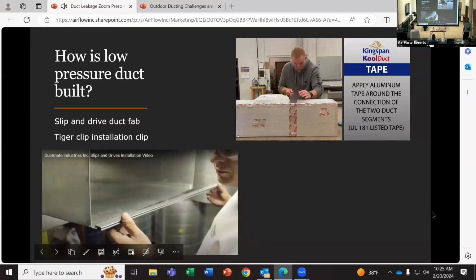You guys get the gist of it, right? So that's low pressure duct. On the left, what he's building right now without any sealer is leakage class 48. What Adam's building on the right is leakage class 3, so 116. Now, we're not gonna let leakage class 48 ductwork get installed on our jobs according to code, so I'm gonna show you guys how we get from 48 to another number. I can go ahead and go back to the presentation.